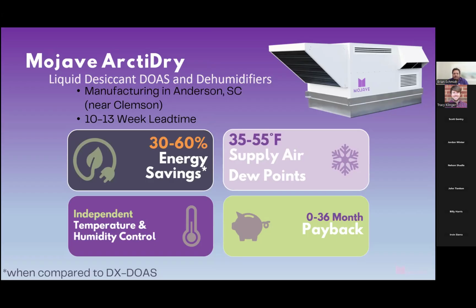As I go through this presentation, I want you to think of whether I'm talking about temperature control or humidity control, because for 50 years, the way that we have manipulated humidity in a building is by manipulating temperature, right? Drive the air down below the dew point, wring out the moisture in the air, use hot gas reheat to space neutral conditions, and you supply the air that you need. Mojave has independent temperature control and independent humidity control, and I'll get into that here in just a little bit.